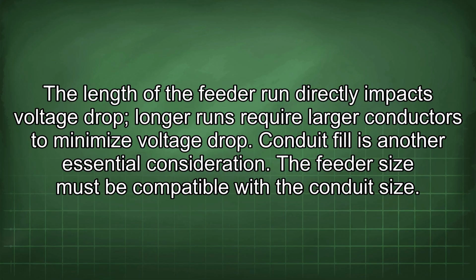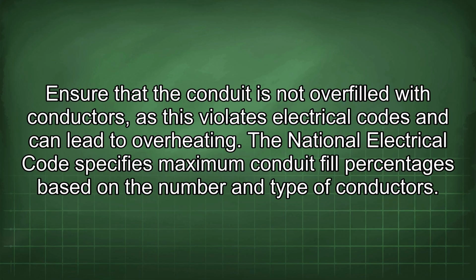Conduit fill is another essential consideration. The feeder size must be compatible with the conduit size. Ensure that the conduit is not overfilled with conductors, as this violates electrical codes and can lead to overheating. The National Electrical Code specifies maximum conduit fill percentages based on the number and type of conductors.